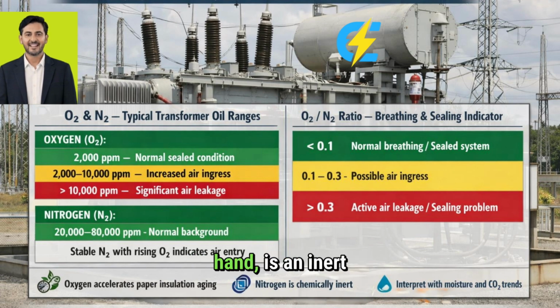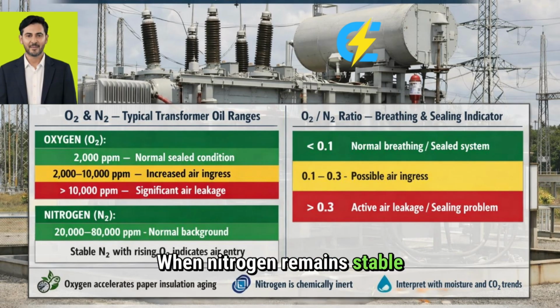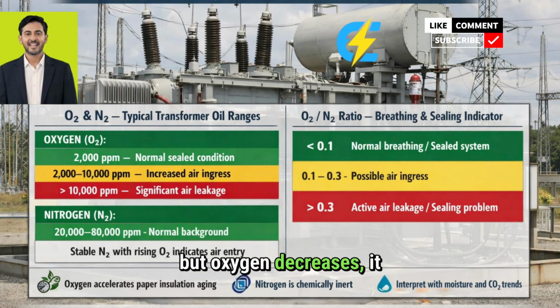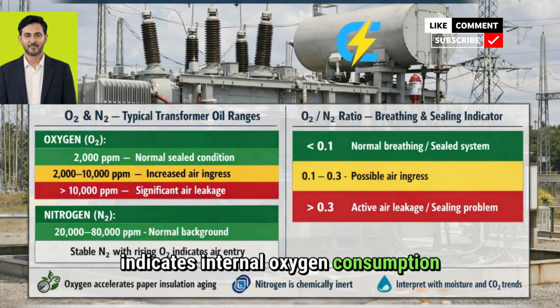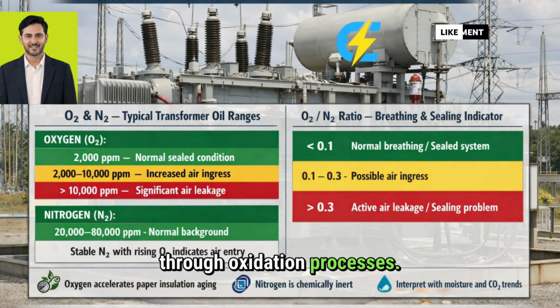Nitrogen, on the other hand, is an inert gas. It does not react with oil or paper. This makes nitrogen our reference point. When nitrogen levels change, it tells us about air ingress. When nitrogen remains stable but oxygen decreases, it indicates internal oxygen consumption through oxidation processes.